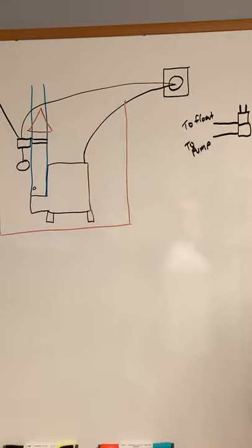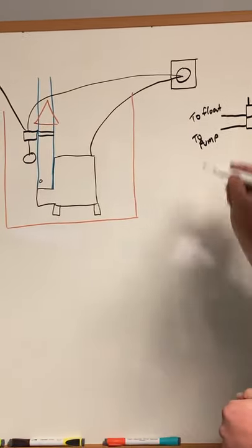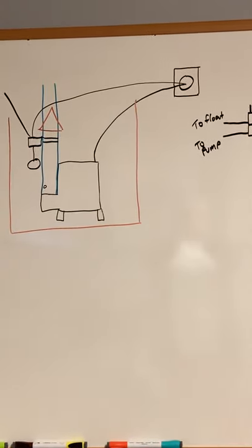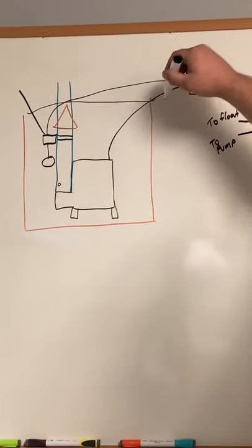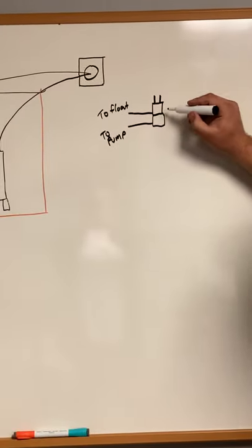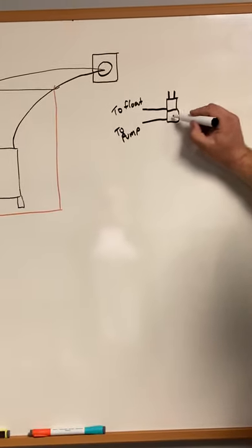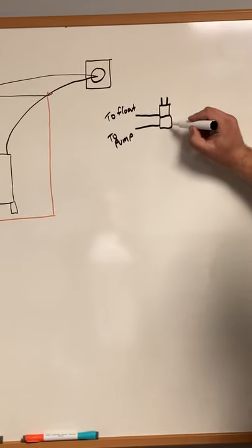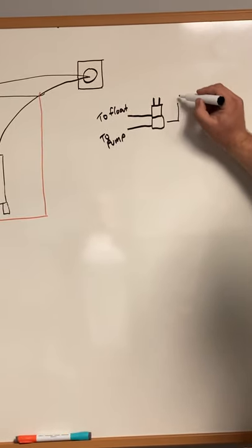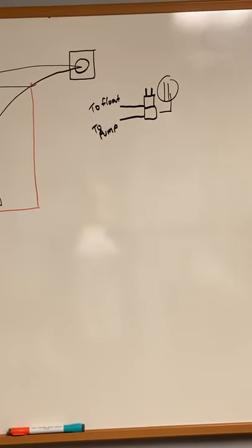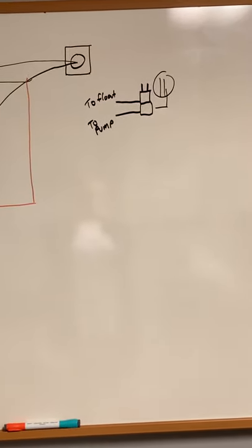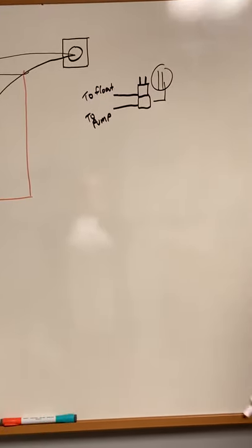So one thing you can do if you walk into your basement and you can see that your pit is extremely full, you know, like filled to the top, ready to run over, is you can actually unplug the pump from this float switch and plug this pump outlet directly into your outlet. And if the pump kicks on, that's great. If not, we've got a pump issue.